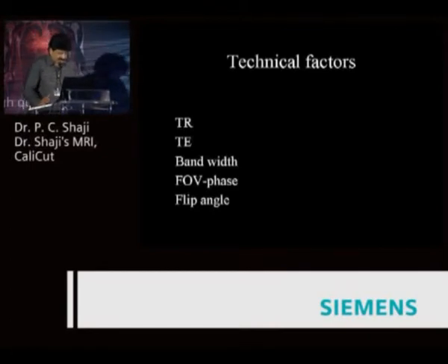And in plane and FOV you can adjust, and for phase FOV you can use a rectangular FOV. When you acquire the images in a rectangular FOV, there can be oversampling errors or wraparound artifacts. But one of the advantages of phased array coils is that the peripheral signals are low, so in a practical sense you may not always see the wraparound artifacts.